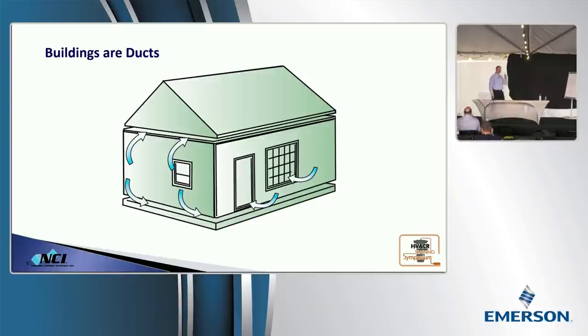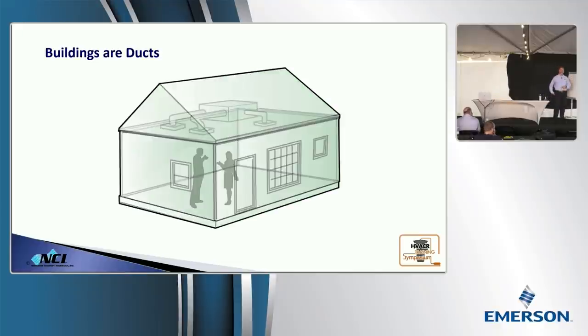There's one variable that we can't measure for and that we have to allow for, though, and that's the occupants. People start living inside the duct system. And when they do, they start changing damper positions. And I'm not talking about dampers in the ducts. I'm talking about conditioned space manual dampers. We call them doors. They start opening, closing doors.